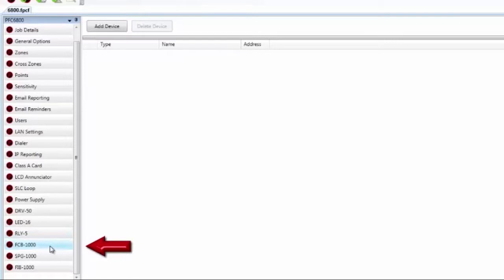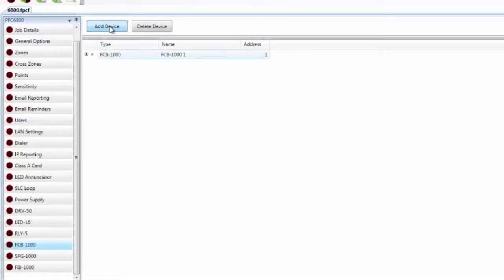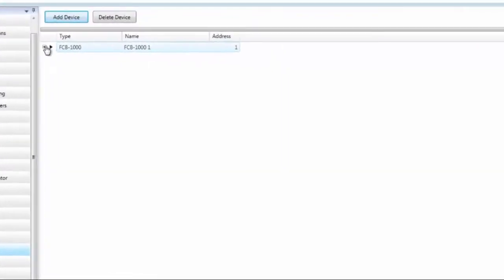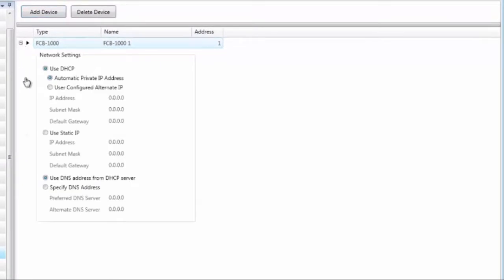Moving to the FCB-1000 — this is the fire communication bridge, the remote Ethernet connection. You can have one connected to any of the systems. Click Add Device to add it and give it a name. The address is 1, and while it will accept any number between 1 and 31, it is recommended to leave it at address 1. Make sure the DIP switch on the FCB-1000 is set to address 1. Expanding the device allows you to adjust the network settings of the FCB-1000.